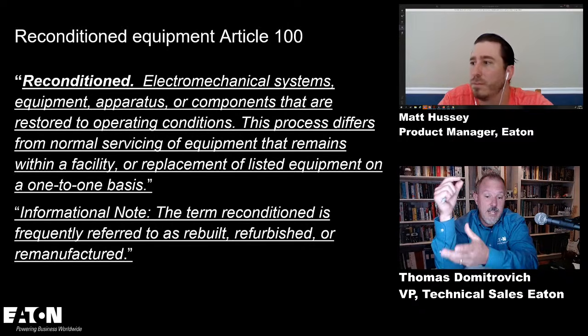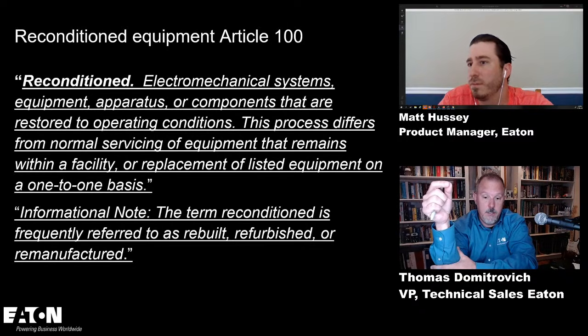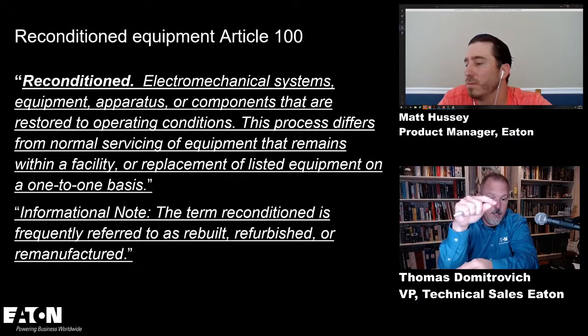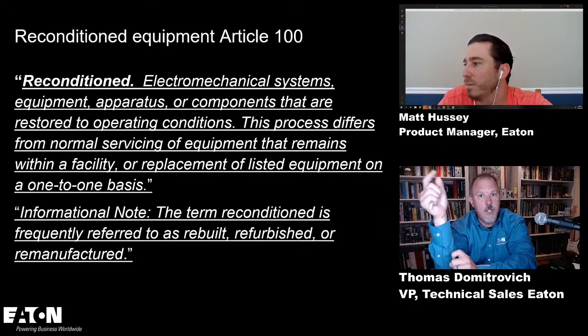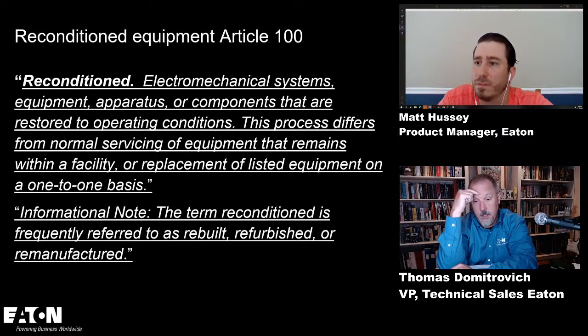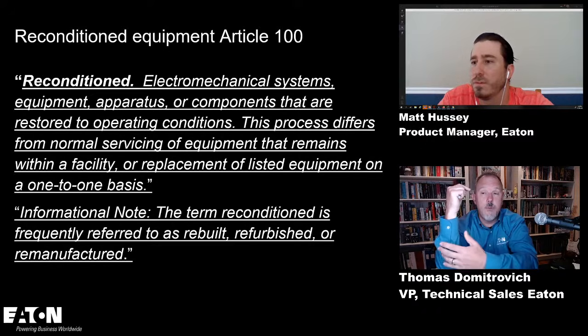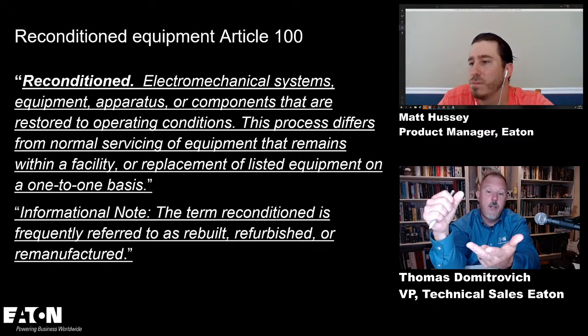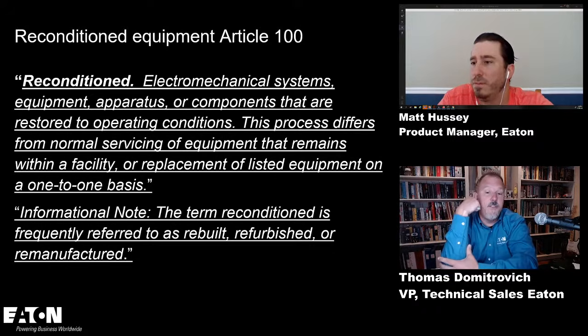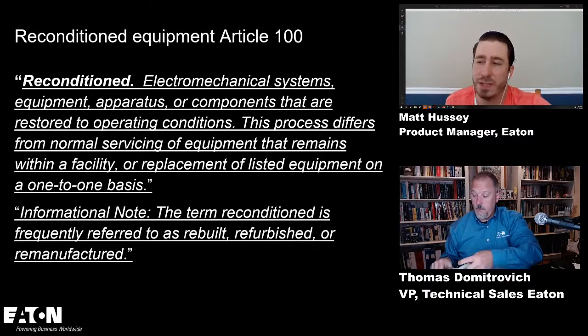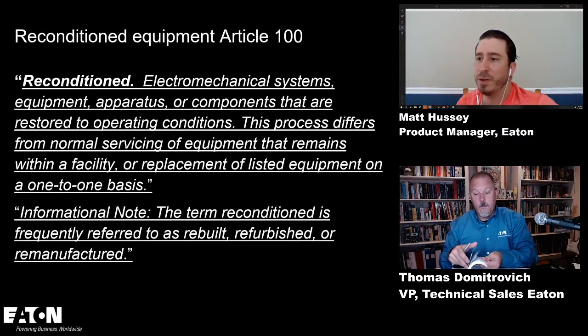So the first sentence in reconditioning establishes that it's any piece of equipment that wasn't working and now, when you get done, it is working. So if I had a motor control center that quit working because of maybe water damage, maybe I hit it with a truck, all that good stuff, can I recondition it and get it back up and running again? You'd probably need to verify how you'd be able to do that. There are some NEMA policies out there for dealing with things like water damage and reconditioned equipment.